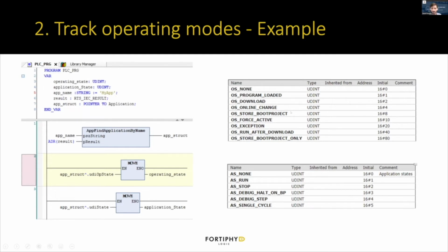So you can see the operating state can be anywhere from program operating state, download, online change, forced active, exception. So very detailed different states of the program, and very useful to log what the current state is and when it changes, to know if the program has changed or if someone has any forced values on the PLC. And in a similar way, the application state, whether it's currently in stop mode or run mode or debug mode.